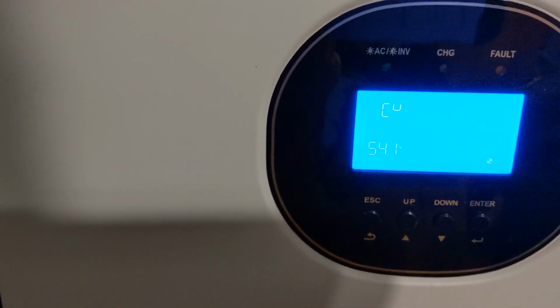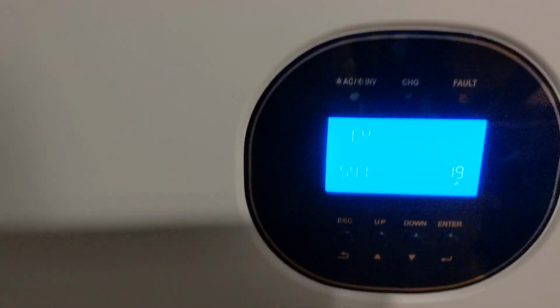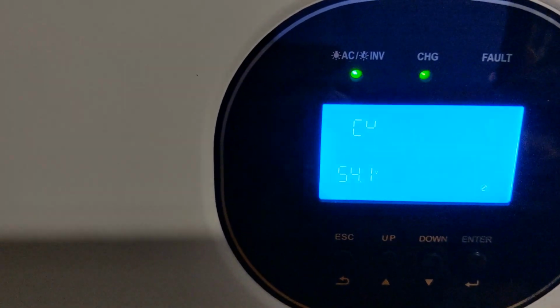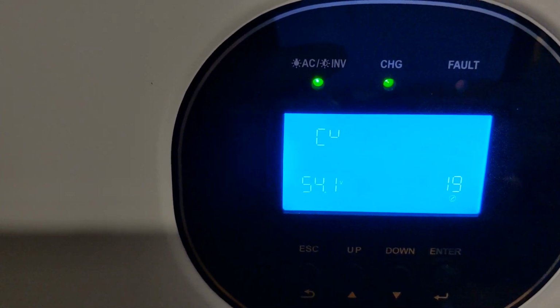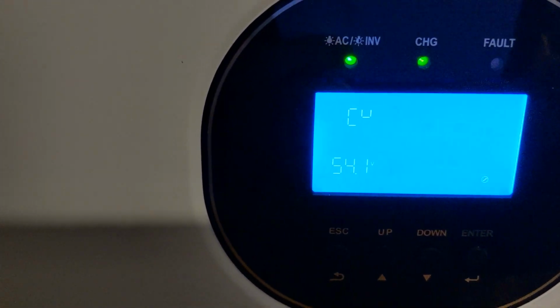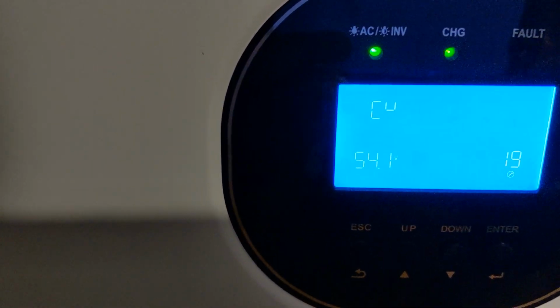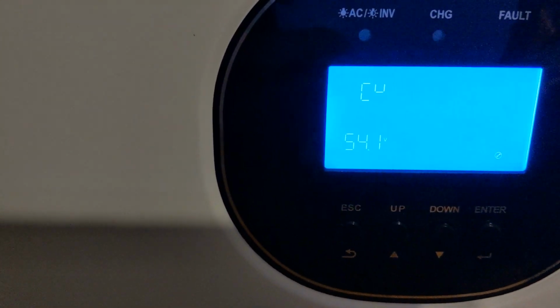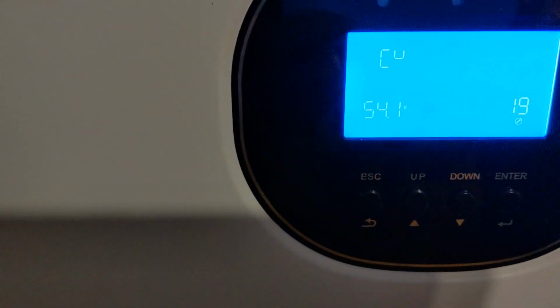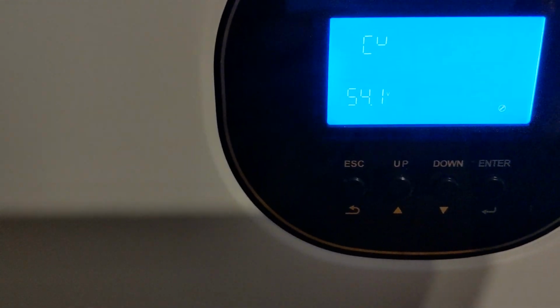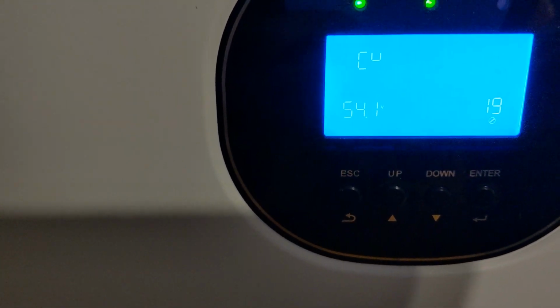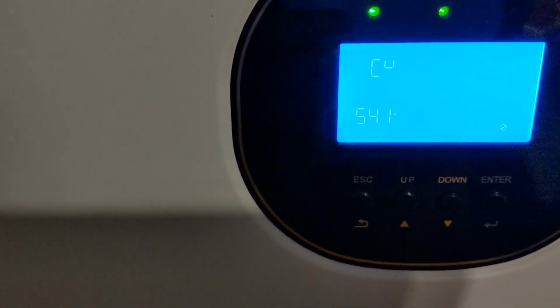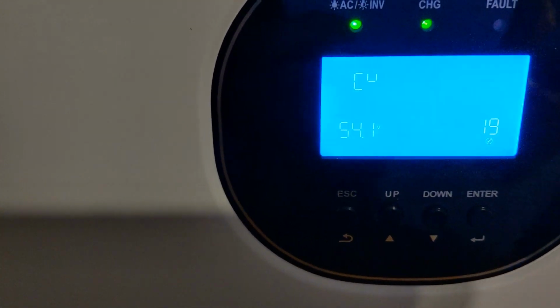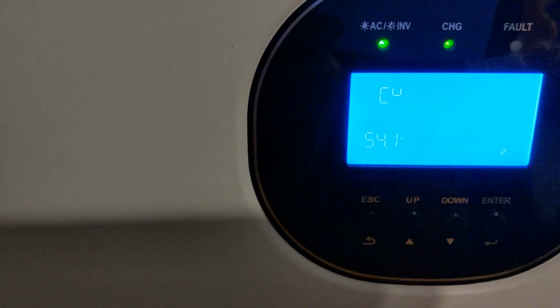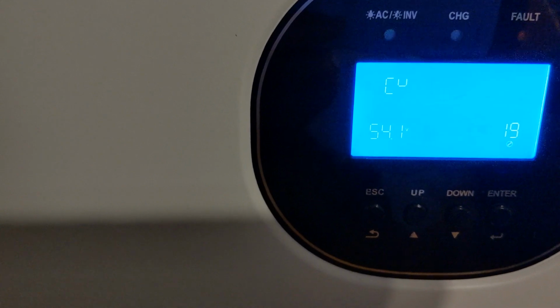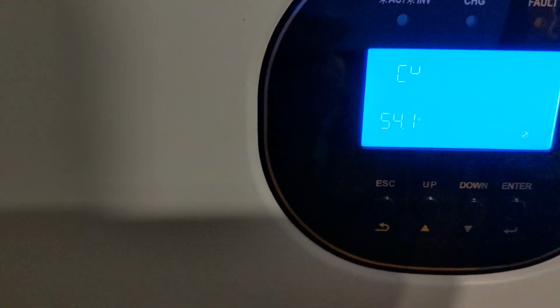Now we're getting down into charging. This is where you set all your charging parameters since you're on a user-defined setting, including your different voltages. In the case of number 19, this is your bulk charging voltage - depending on what value you need to charge your batteries up to, this is where you'd set that. Since I'm keeping my batteries fairly conservative, I have my bulk charging set at 54.1, so it does its peak charging up through that point.